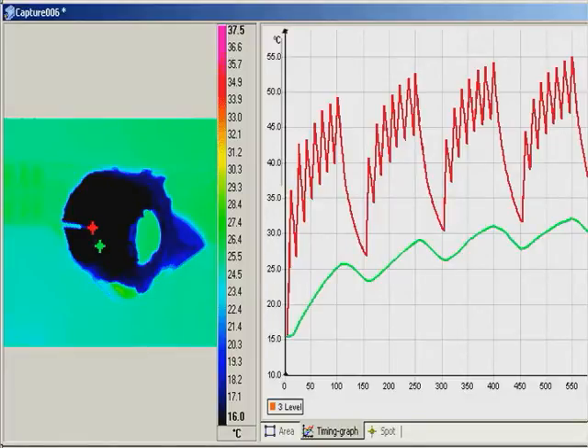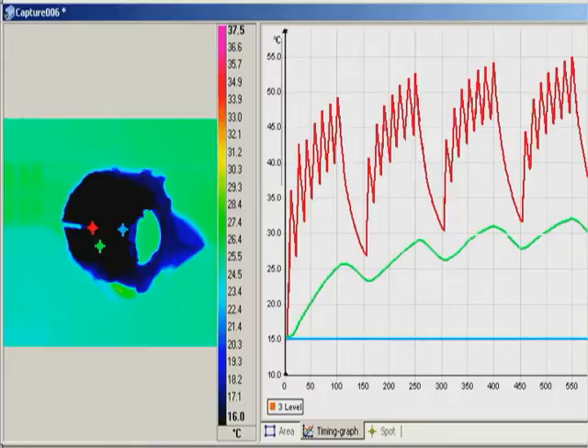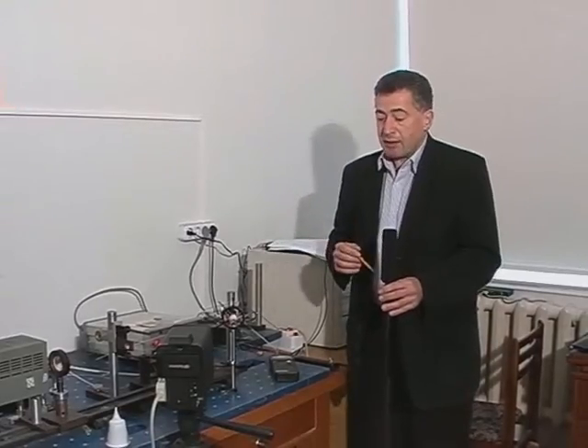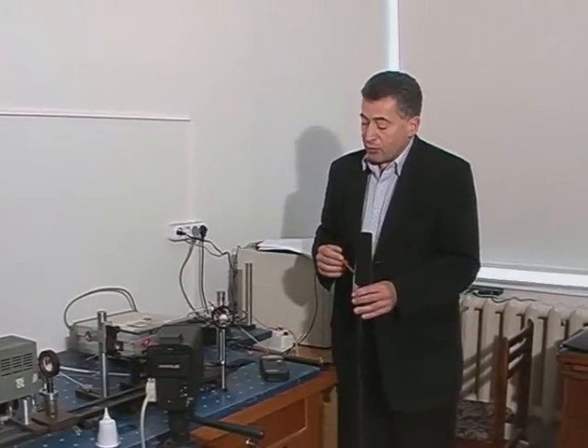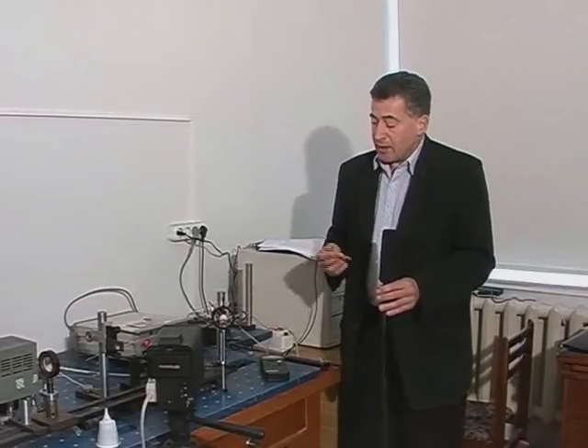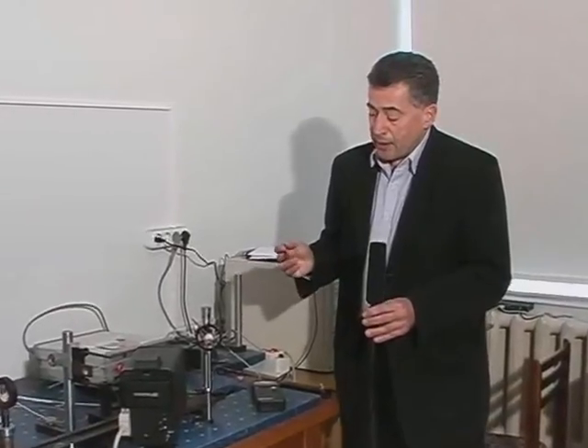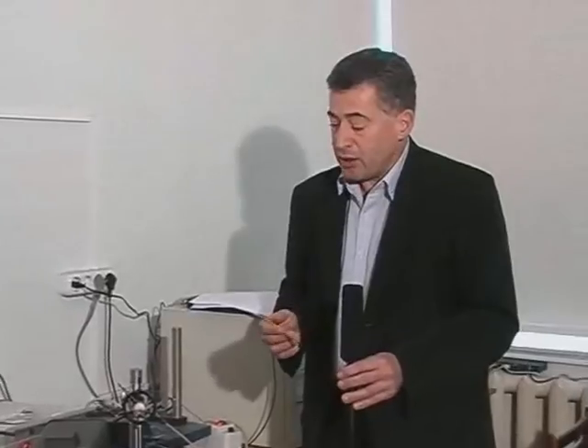The results of temperature measurements prove that the laser effect is local and controllable. The amplitude of the temperature oscillations diminishes with distance from the laser spot and there is no heating at all at the spinal channel. As a result of comprehensive studies during more than 10 years, specific regimes and parameters of laser irradiation of the disc were established, which activate the reconstruction of the disc while simultaneously preventing any undesirable side effects.